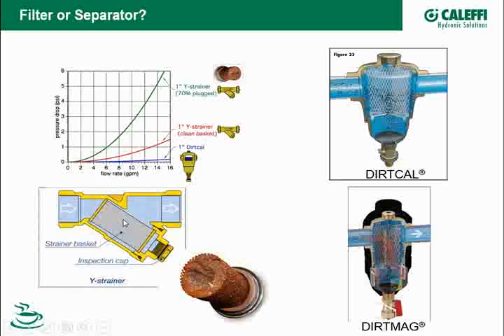And the other thing to know about these, as they start plugging up, as they start doing their job and filtering out the dirt and debris in there, they're going to reduce the flow going through. In fact, here at 70% plugged, you can see what it does to the pressure drop of that Y strainer. So if you are using this type of device, just go back and disassemble them, or at least put a valve in here that you can blow them down and flush them down, because you've got to clean those out occasionally if they're doing their job.